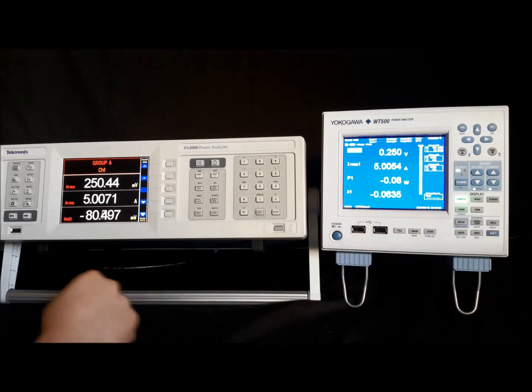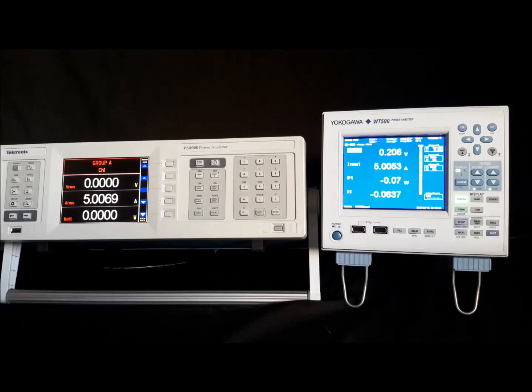Whereas the lowest range on the 500, I believe, is at 15 volts on the screen, 15 volts auto. So let's see how low the Yokogawa can go. 0.1. Let's go to 0.5. Okay, so that's cut off at 0.5. Let's go up to 0.7, 0.8, 0.8. Let's go down to 0.75. Okay, 0.76. 0.75 then blanks after about a tenth of a second. Okay, so let's go with 0.76. But 0.076 out of 15 volts, that's 76 millivolts out of the 15 volt range. That's pretty good.